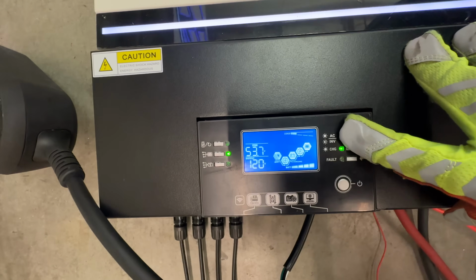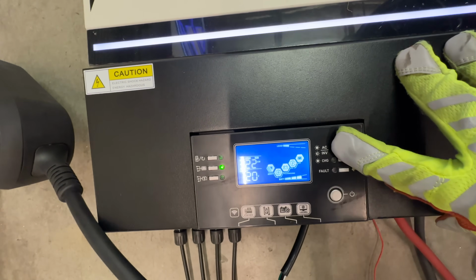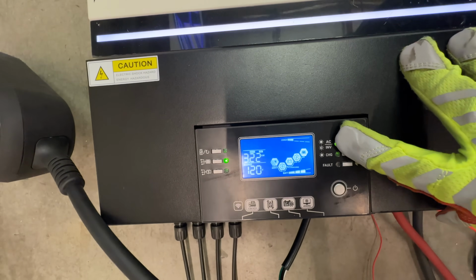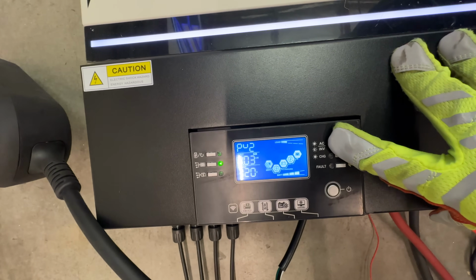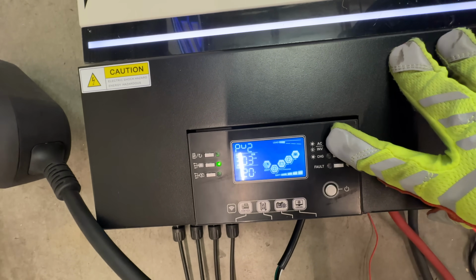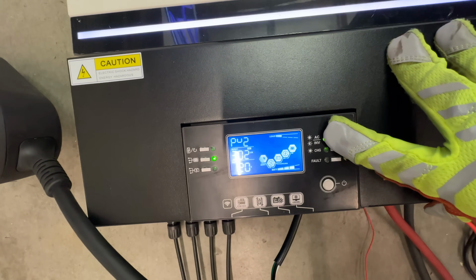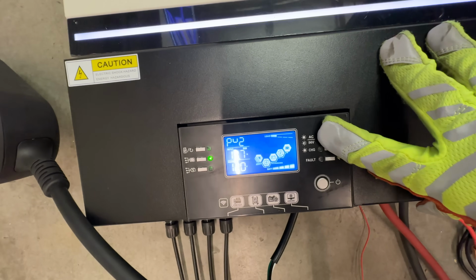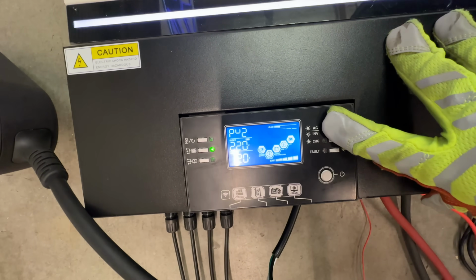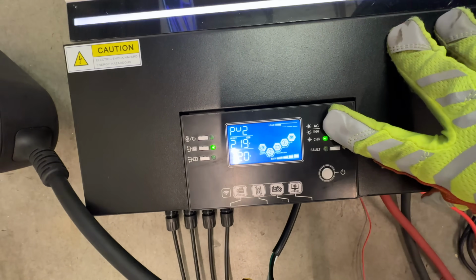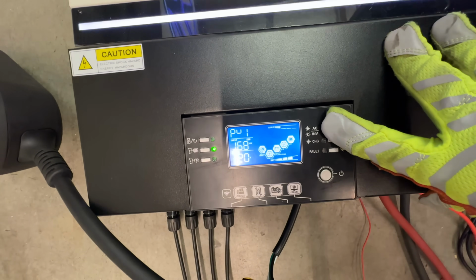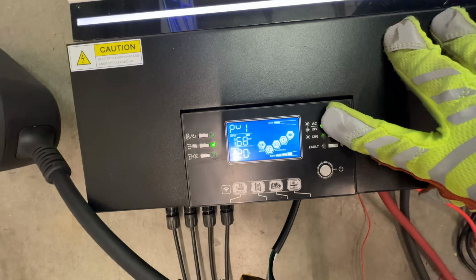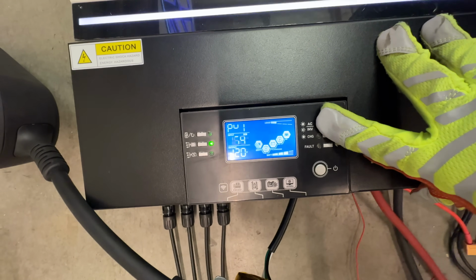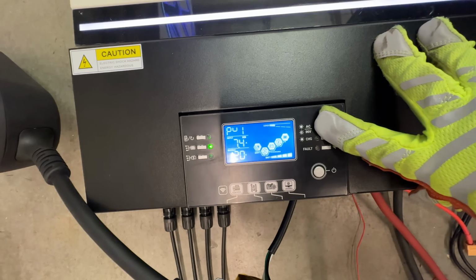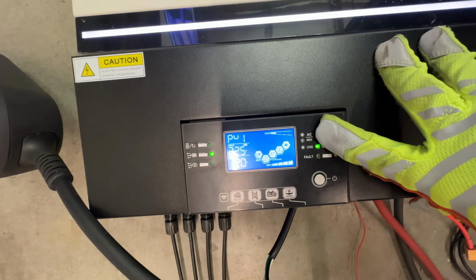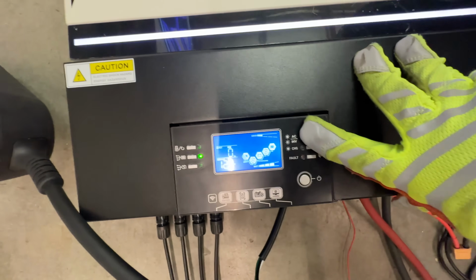Okay, so let's look at this thing. Okay, 3.22 kilowatt. Okay, so PV2, it's got 3.03 kilowatt input coming in. PV2, it's 13.7 amps. PV2, yeah, 212 volts. PV1 is 1.68 kilowatts. Okay, so that one's limited for some reason. 7.4 amps at 226 volts.